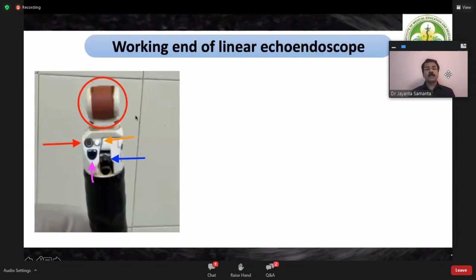So we use this balloon for inflating water in order to get a better echo interface between the transducer probe and the gut wall, so as to maximize the EUS image. For all practical purposes, the balloon is used more with a radial echo endoscope as compared to a linear echo endoscope.